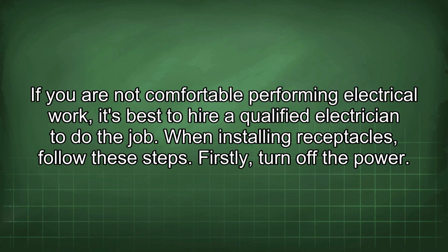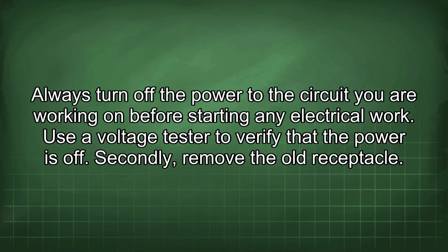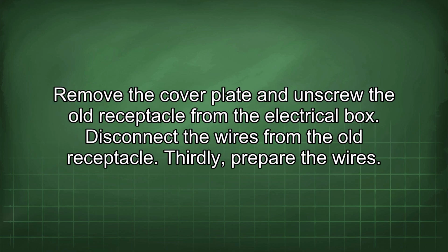When installing receptacles, follow these steps. Firstly, turn off the power. Always turn off the power to the circuit you are working on before starting any electrical work. Use a voltage tester to verify that the power is off. Secondly, remove the old receptacle. Remove the cover plate and unscrew the old receptacle from the electrical box. Disconnect the wires from the old receptacle.